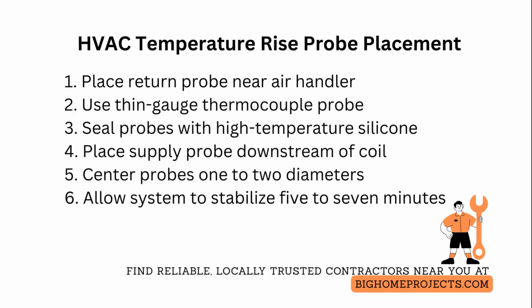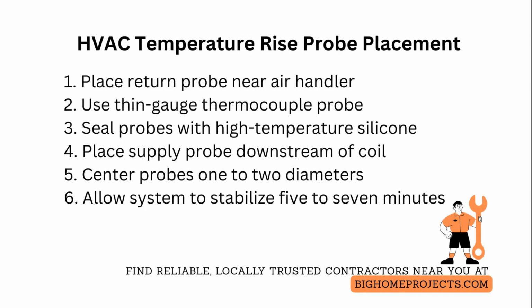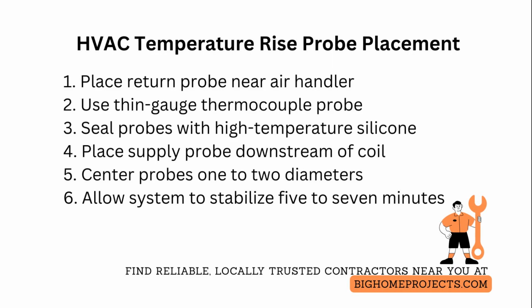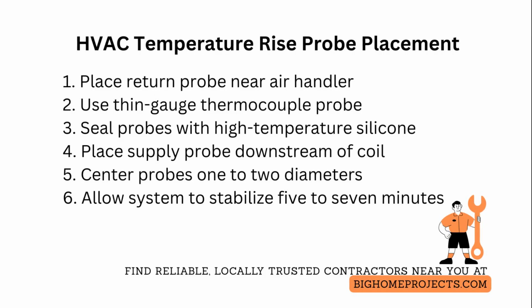Readings. Use a thin gauge thermocouple or thermistor probe and insert it through a snugly sized drill hole, then seal with high temperature silicone so no leakage or stratification alters the reading. The supply probe belongs downstream of the heater coil and the air handler heat exchanger, but not directly in the heater's radiant line of sight.